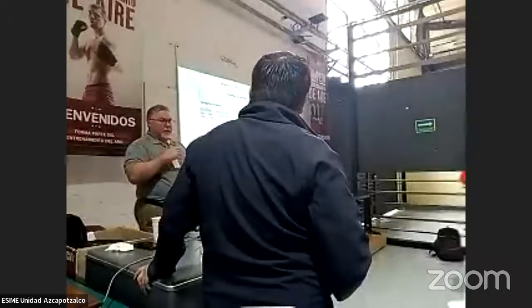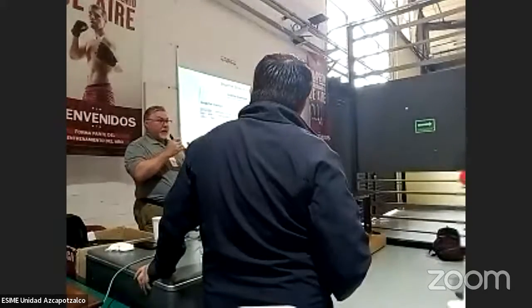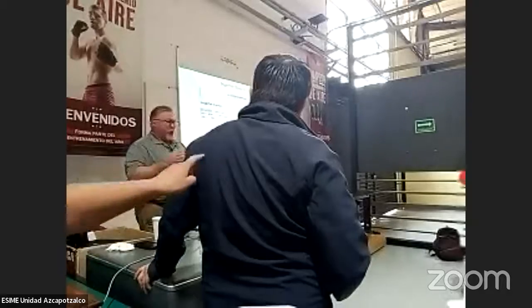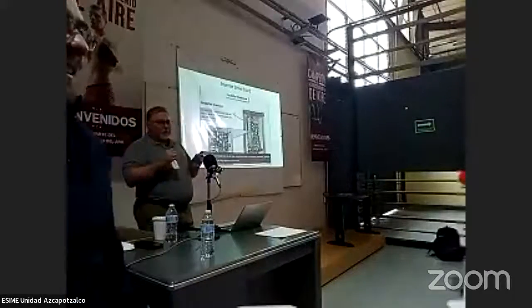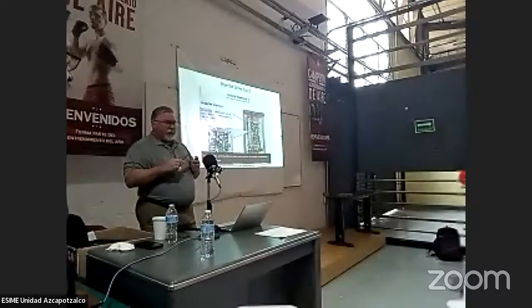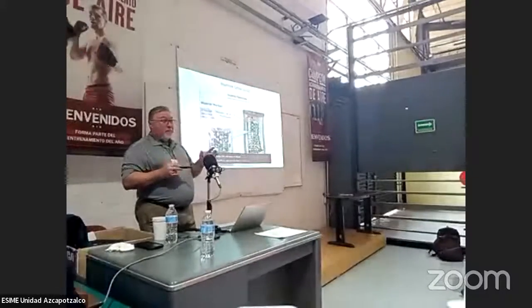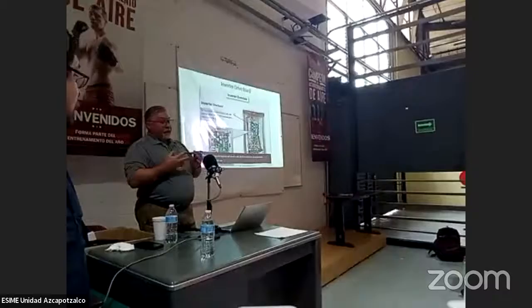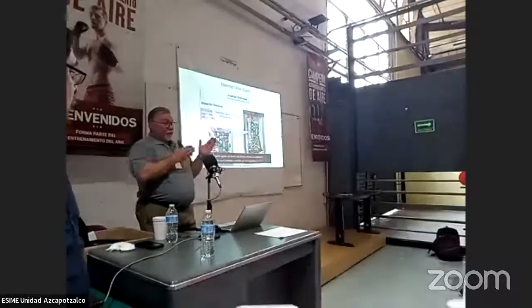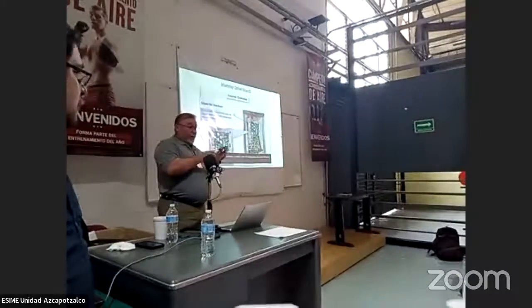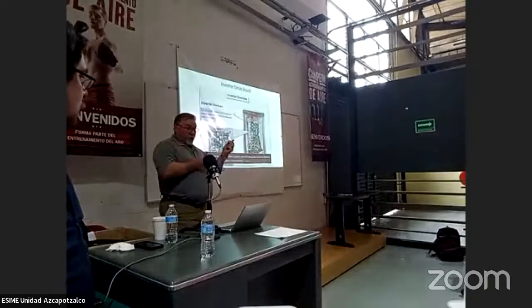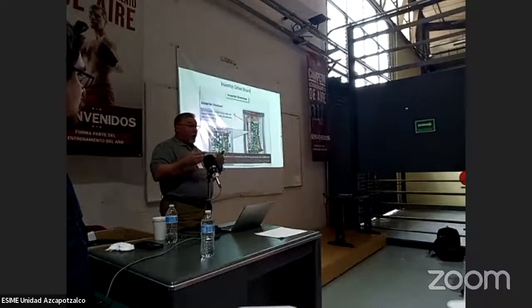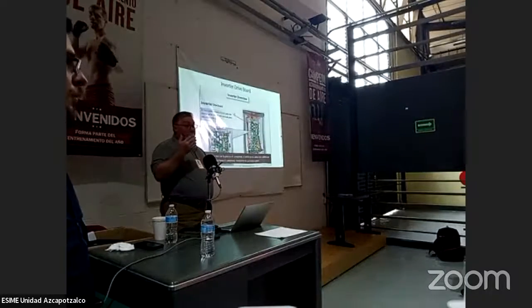Yeah, well, mostly, but I think one of our compressors operates at a higher range. So as long as you check it and it's within range, then the compressor probably is not the problem, unless it's locked up. That's the only other thing. So it's either going to be the board or the compressor, or it could be the cable, the wires going from the board to the compressor. Make sure they all come out properly as well.